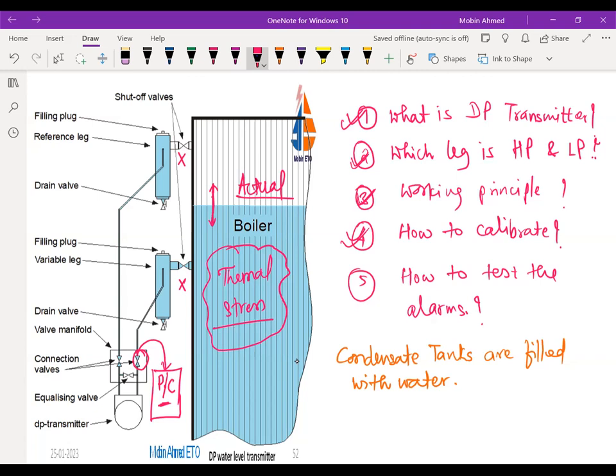How are you going to do it? With the drain valve only you are going to do it for the low level and the low level trip. Again, I am telling, close this. Here the drain valve is there. Release some of the water from here, and thereafter you can release from here also. So steam pressure is out. And thereafter you drain from here and you can check the low water alarm and low water trip.